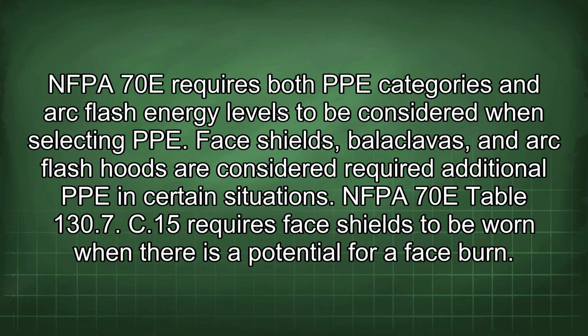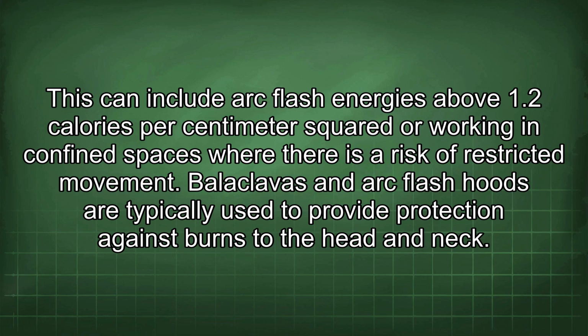NFPA 70E requires both PPE categories and arc flash energy levels to be considered when selecting PPE. Face shields, balaclavas, and arc flash hoods are considered required additional PPE in certain situations. NFPA 70E Table 130.7 C15 requires face shields to be worn when there is a potential for a face burn. This can include arc flash energies above 1.2 calories per centimeter squared or working in confined spaces where there is a risk of restricted movement.